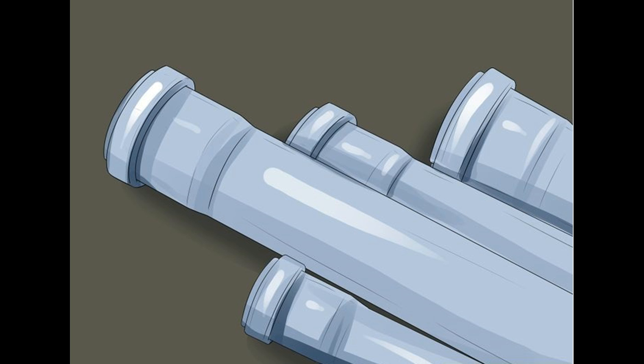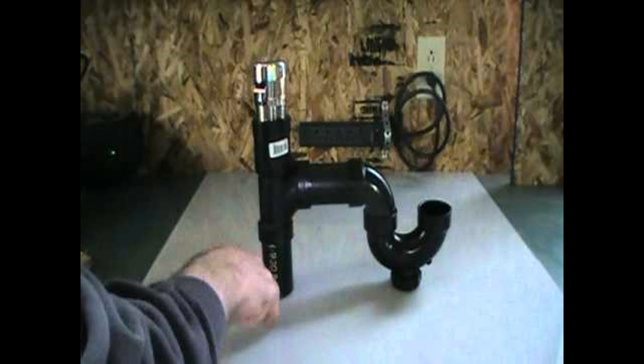Understand how vent pipes work. Vent pipes run from waste or drain pipes upwards, ending outside the building, usually sticking up through the roof. This allows unpleasant and potentially dangerous odors or fumes to safely leave your plumbing system, escaping harmlessly into the air outside. It lets air into the system, filling the vacuums left by water moving through the pipe. This allows water to flow quickly and smoothly through the pipes.